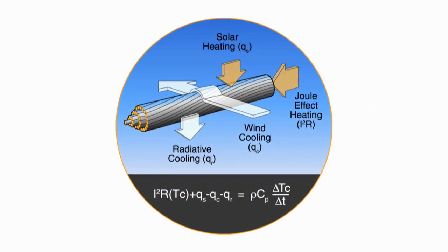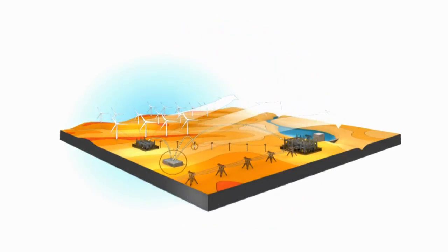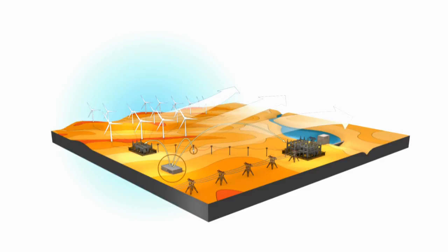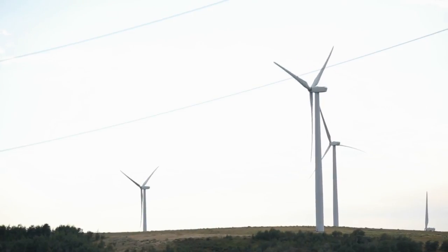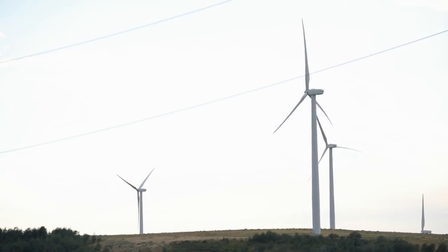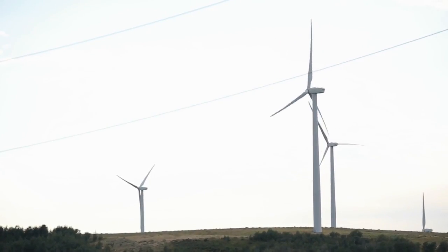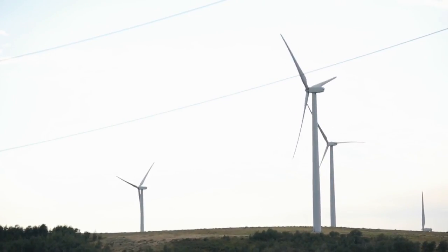Traditionally, the amount of power transmitted through lines is bounded by static limits set with conservative weather assumptions. Yet varying environmental factors can change the amount of cooling on power lines and allow for increased current loads. In fact, lines near wind farms are ideally suited to handle extra electricity generated on windy days.